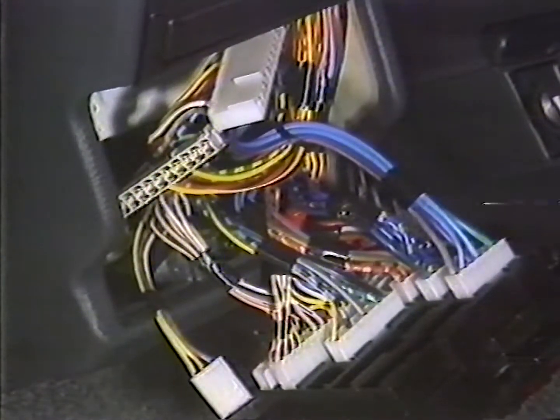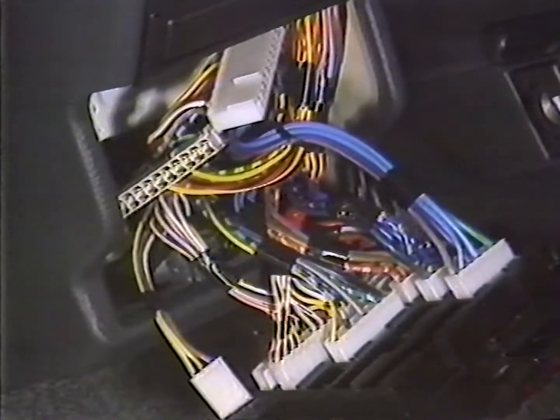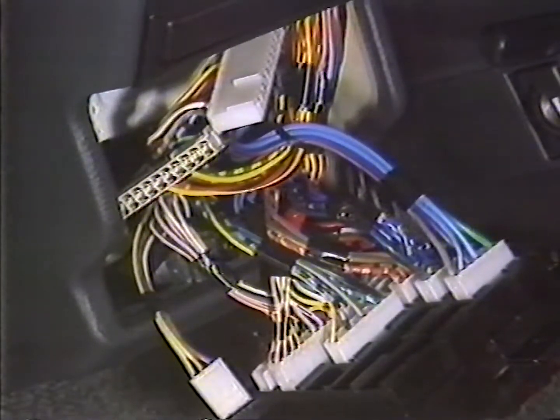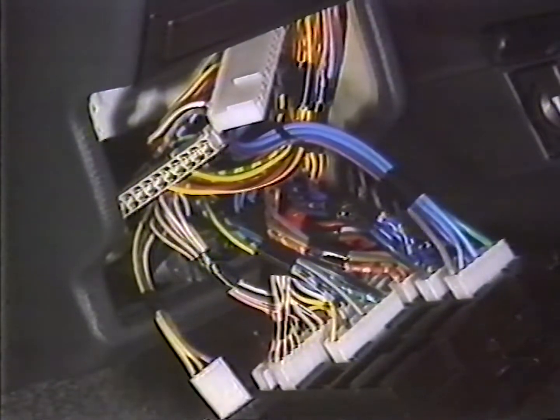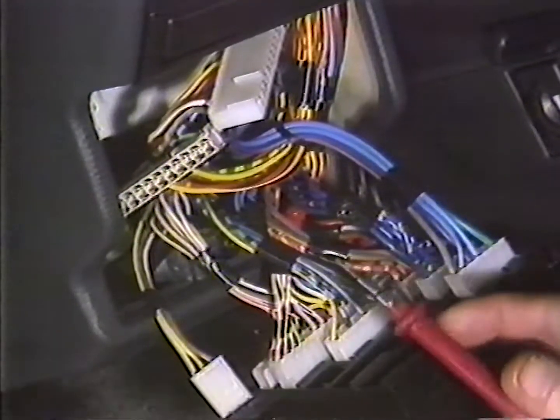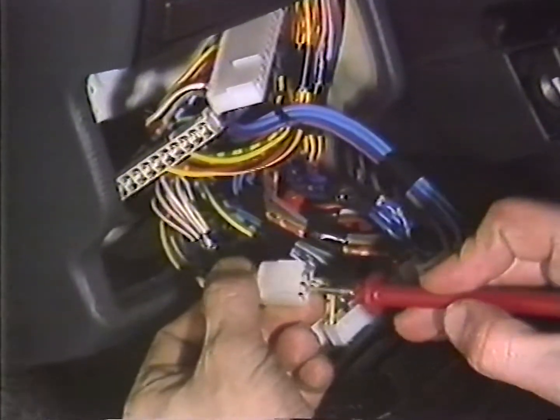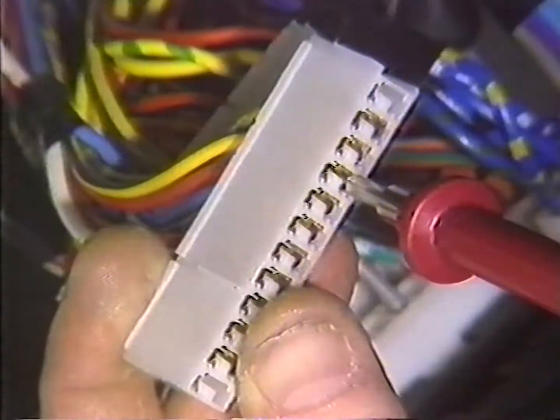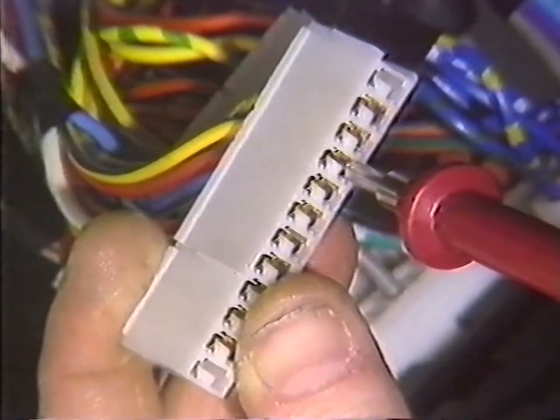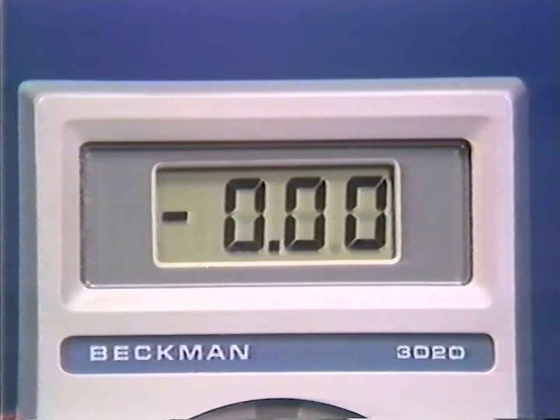We'll use an ohmmeter to carry out the check. One of the instrument's probes should be connected to earth, whilst the other should be connected one by one to the supply leads for the various items of electrical equipment. On the item affected by a short circuit, the instrument will show a resistance reading of 0, 0.